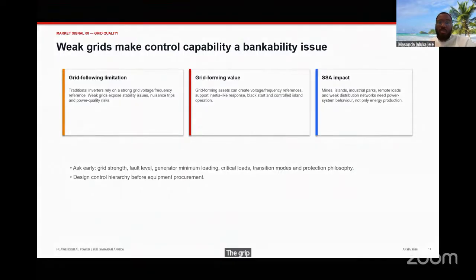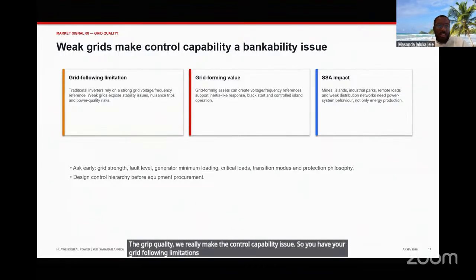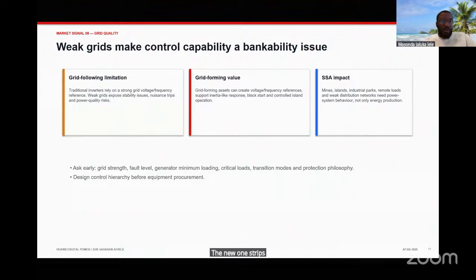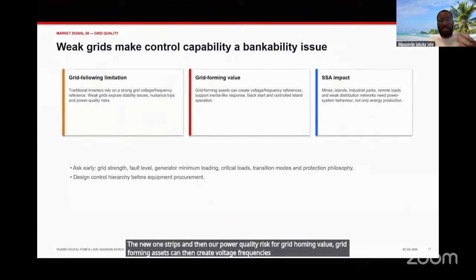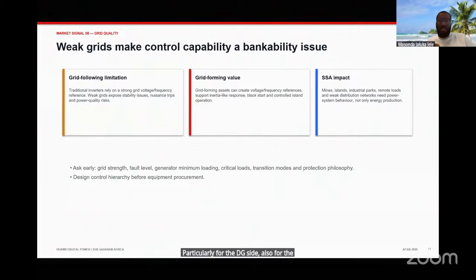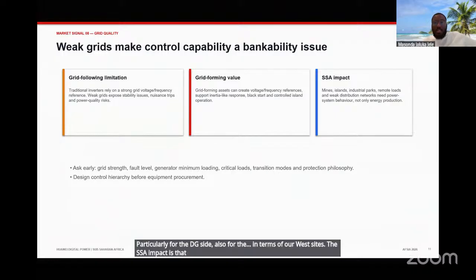On grid quality, weak grids make control capability a bankability issue. So you have your grid-following limitations. Traditional inverters rely on a strong grid voltage and frequency reference. Weak grids then expose stability issues, nuisance trips, and power quality risk. For grid-forming value, grid-forming assets can create voltage and frequency references and inertia, black start, and control islanding, which are some of our key features that we offer, particularly for the DG side. The SSA impact is that mines, islands, industrial parks, remote loads, and weak distribution networks need power system behaviour, not only energy production.